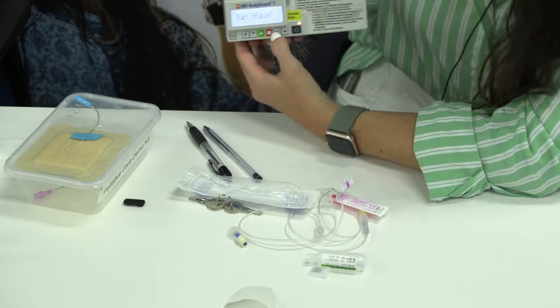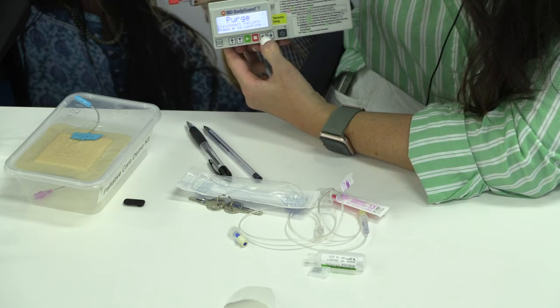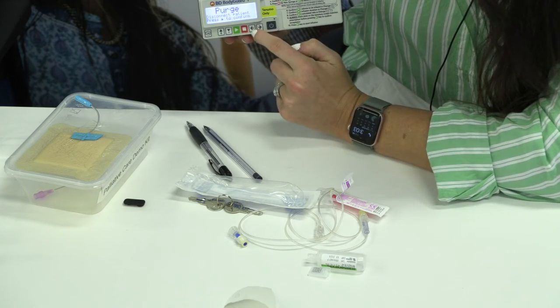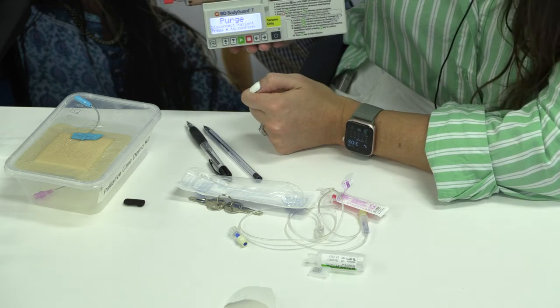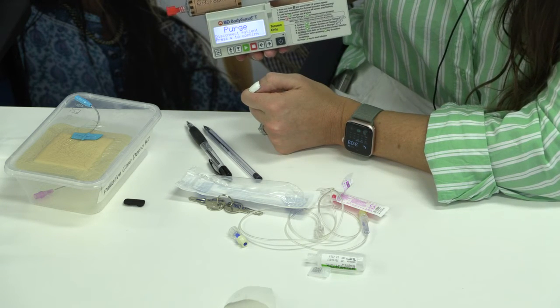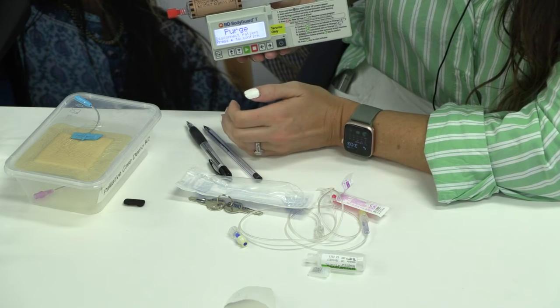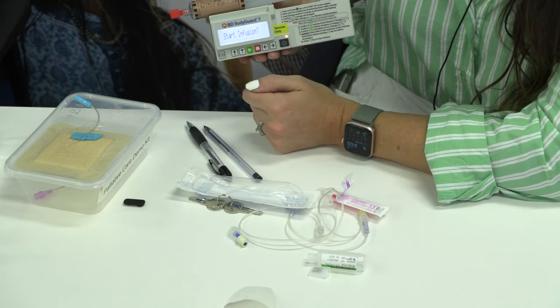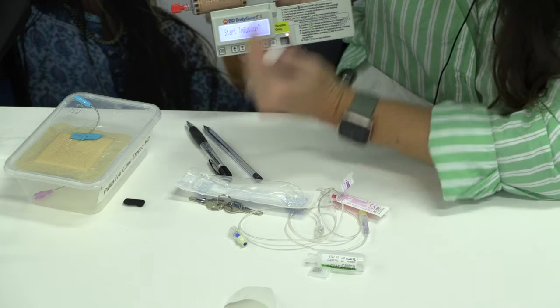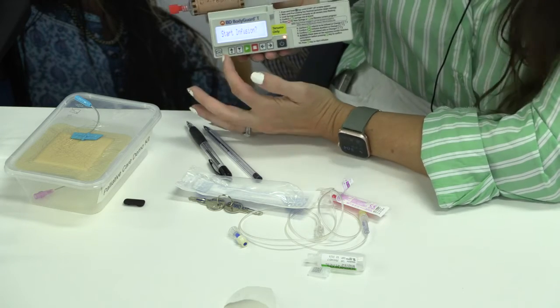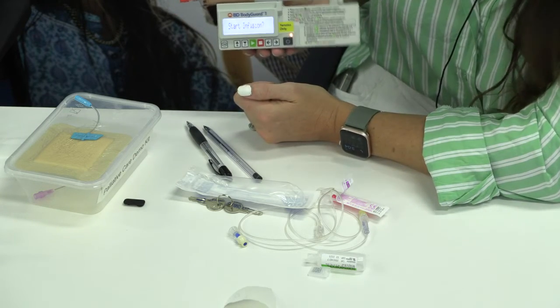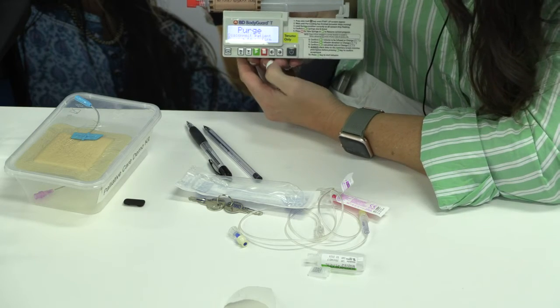Sorry, I'm just going to have to turn. You press the forward arrow button and it says purge. We don't manually purge the lines because that can throw out the calibration. So we always want to let the machine do the calibration and the purging for us. If you don't do it quick enough, it'll just revert back to the start infusion page, so we can just press the purge button again.